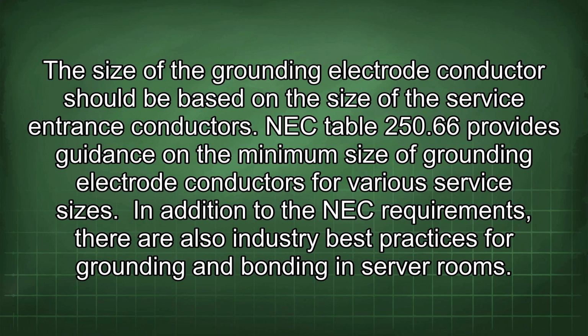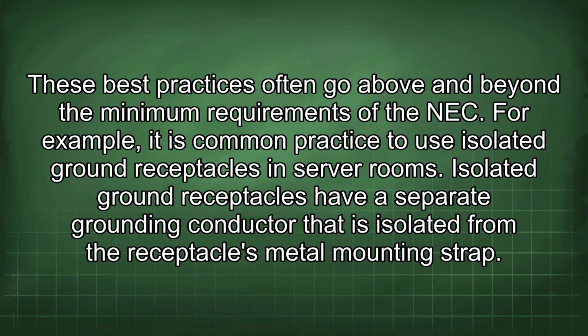In addition to the NEC requirements, there are also industry best practices for grounding and bonding in server rooms. These best practices often go above and beyond the minimum requirements of the NEC. For example, it is common practice to use isolated ground receptacles in server rooms.